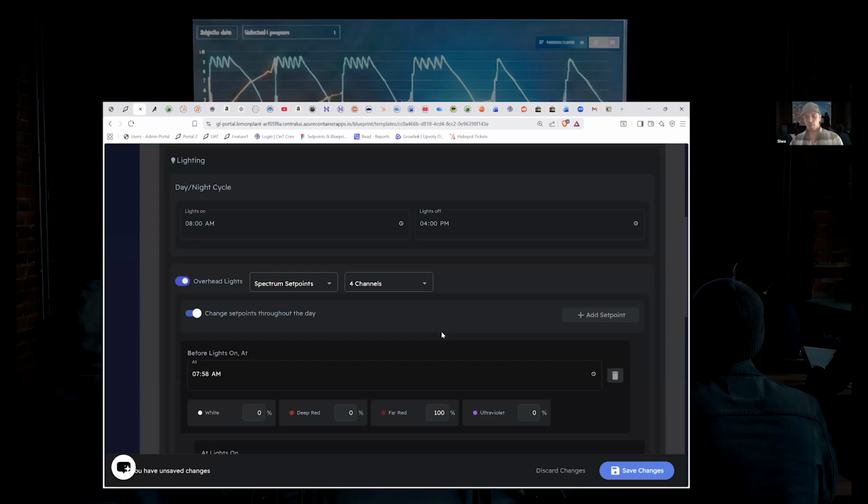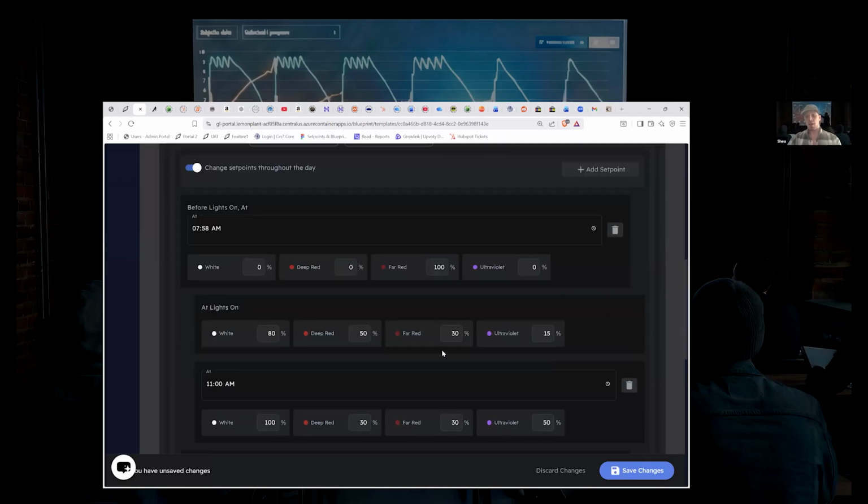Perfect. And then Julian asked a question I'm just going to answer live. He was asking what type of HVAC units we can control. Ray had said we can control things off of dry contact relays, BACnet IP, BACnet MSTP. We're also working on Modbus right now as well. If you have Modbus units and you want to control them, we can usually work with you and some third-party integrator to integrate those as well. So, yeah, just wanted to clarify that for the group in case anybody else had that same question.